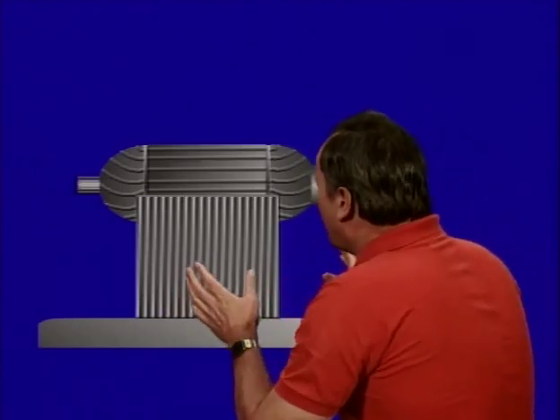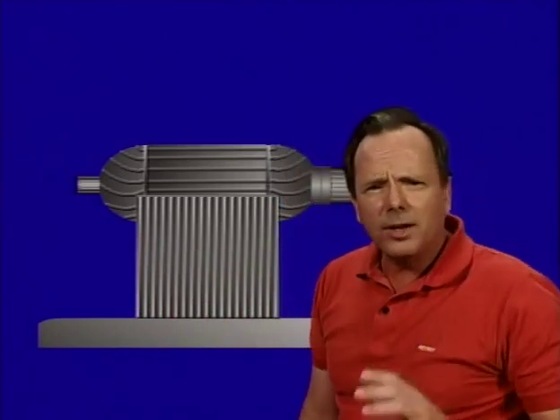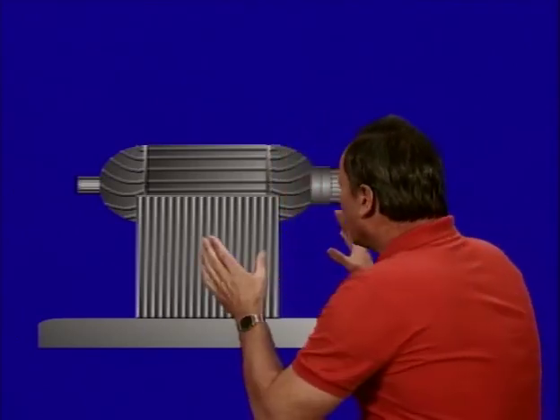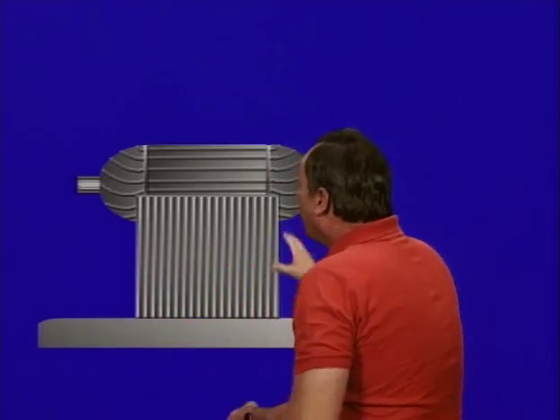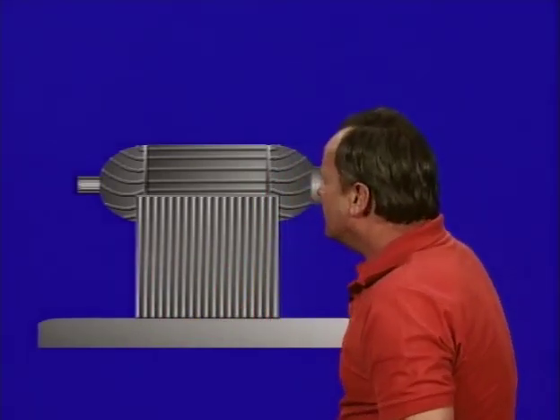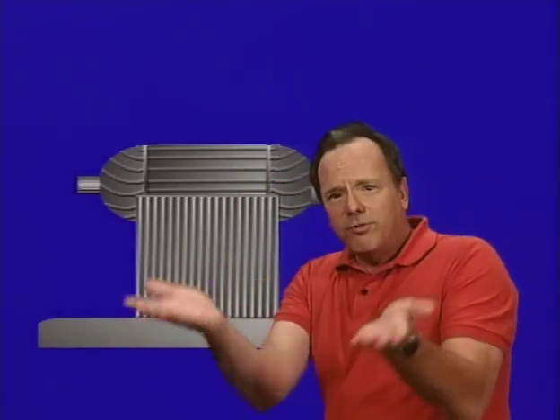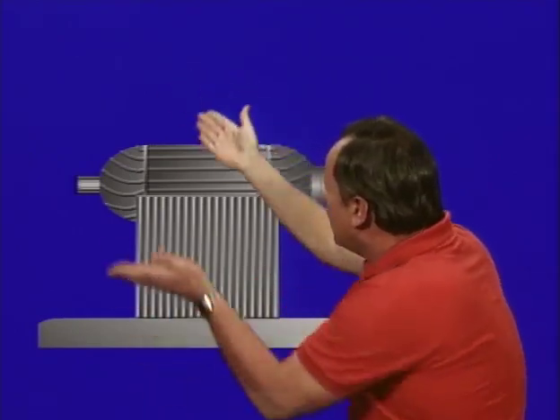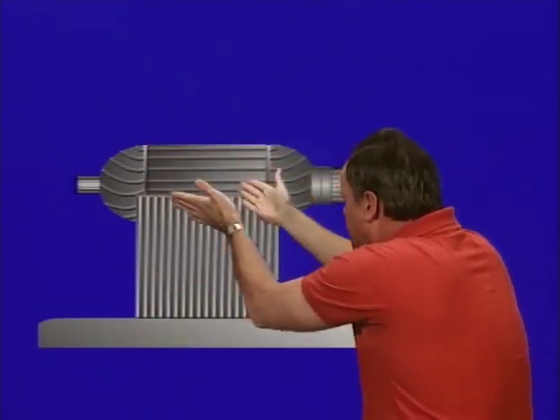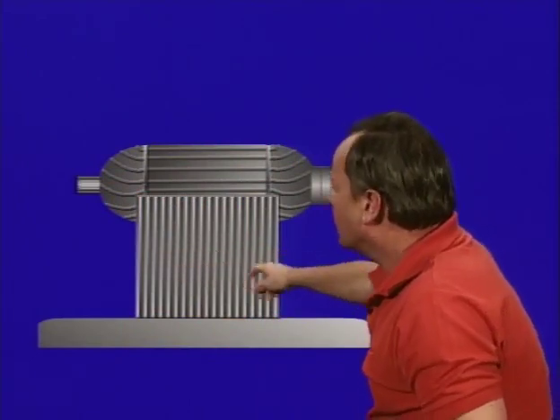So you can test for that by using a device known as a growler. I want to point out right now, a growler is not a reference to my personality in any way at all. Maybe on some Monday mornings, yes, but not generally. I am not a growler. That's a device designed to test an armature. And what a growler is basically a coil with a V in it so that you can put the armature in that coil. It sits down in the coil with a V shape here, and you connect the growler to 110 volt AC, and when you do that, it makes a humming noise or a growling noise, and that's why it's called a growler. Very good, very good.